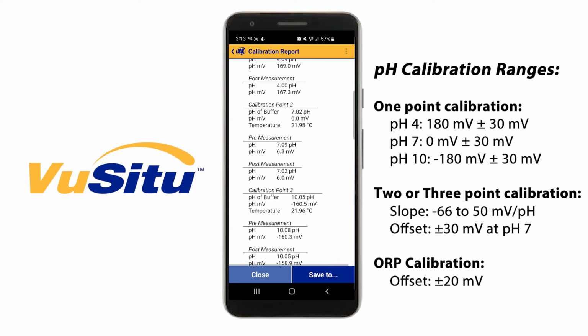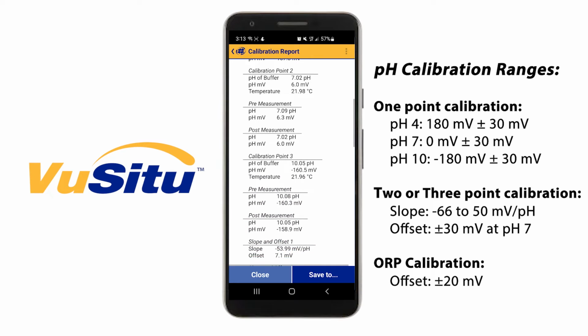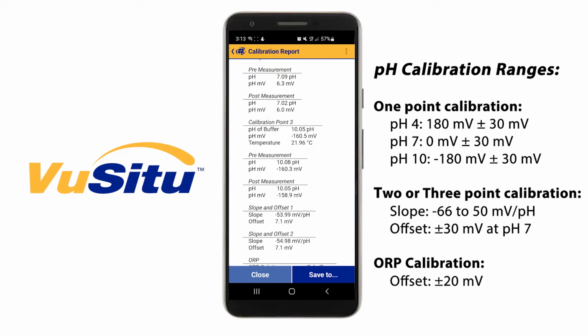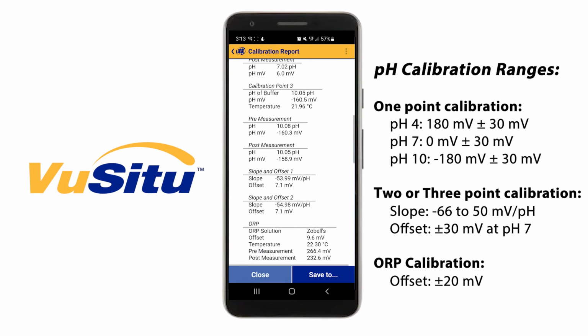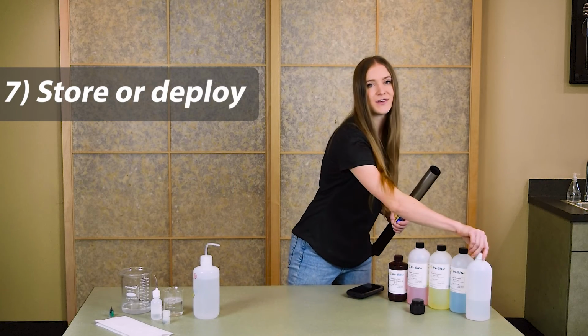If any of the values are out of range, you might need to check that no air bubbles got into the sensor during the filling process or replace the reference junction. Then try your calibration again. If any of the values are still out of range, it may be time to replace your sensor. Assuming your calibration values are in range, you're ready to either store or deploy the sensor.